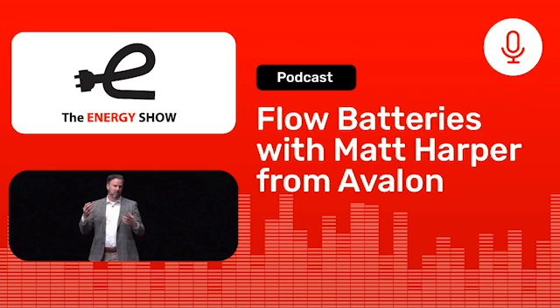It really depends on how much you're using the battery. The pumps we use are designed for something like 80,000 hours of operation. So if you're running the battery 24/7, that means after about 10 years you might need to replace those pumps. But practically speaking, in most applications you're not going to run the battery 24 hours a day. If you think about an application where you're self-generating your own electric power off of PV in the middle of the day and then using the battery to cover a load in the evening, your battery's probably going to be operational for 6 to 8 hours. That means you're going to get 20 to 30 years out of components like those pumps.